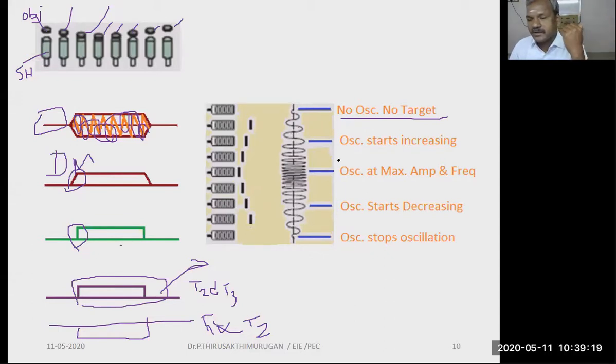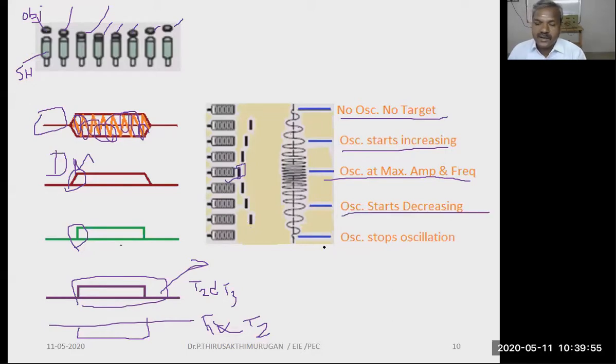When there is no target, there is no oscillation generated by the oscillator. As the object appears near the sensor head, oscillation starts increasing. The oscillation is maximum, with maximum amplitude and frequency, when the object is very close or even on the sensor head. When the object starts leaving the sensor head, the oscillation starts decreasing, and when there is no object, the oscillation stops.